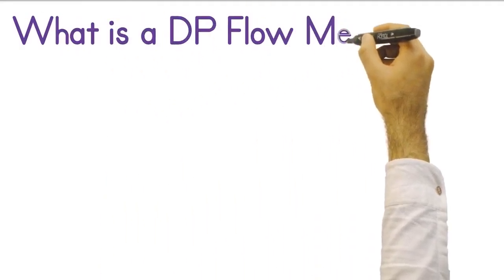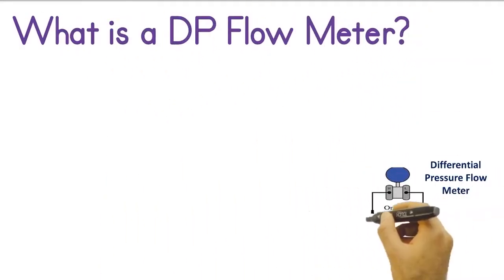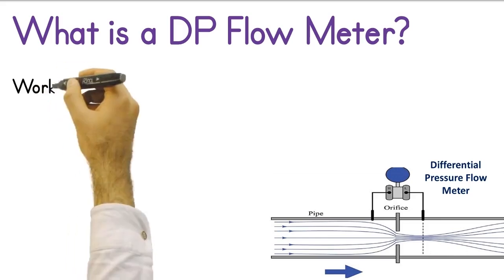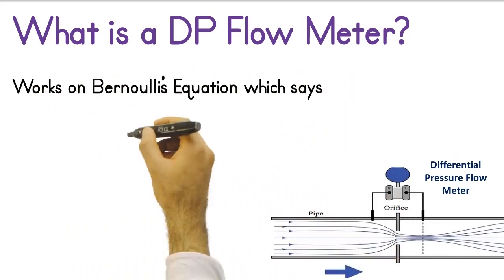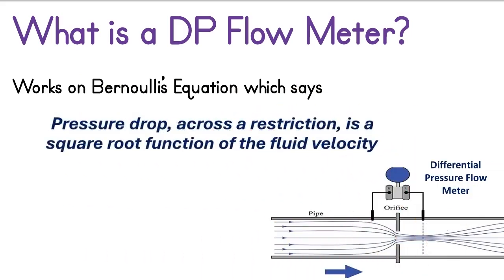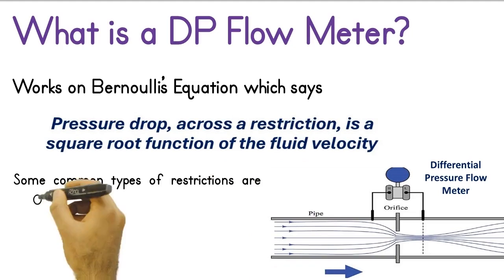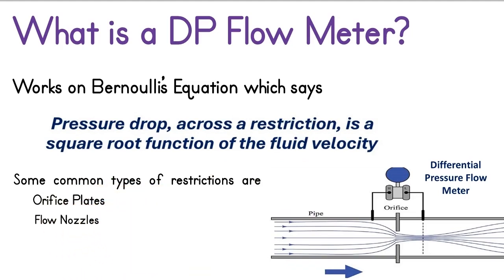What is a DP flow meter? In a differential pressure flow meter, the flow rate is calculated by measuring the pressure difference created by the flowing fluid. It works on Bernoulli's equation, which states that the pressure drop across a restriction is a square function of the fluid velocity. A restriction is inserted in the pipe to create a pressure drop. Common types of restrictions include orifice plates, flow nozzles, venturi tubes, and pitot tubes.